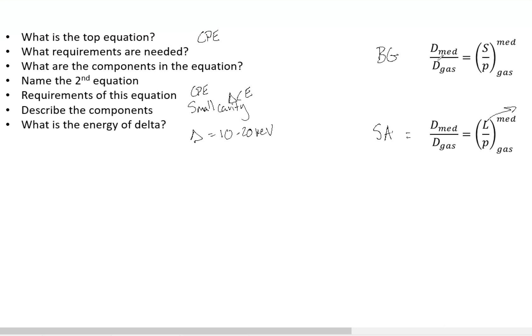Know that this is the foundation of TG-51. Now we have a bunch of extra correction factors and things in TG-51, but ultimately, this is what everything is based off of. So it's very important to understand that fact.